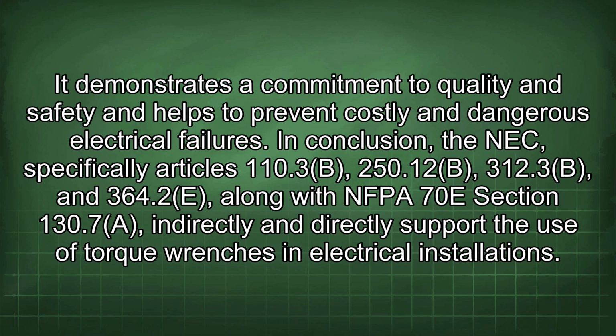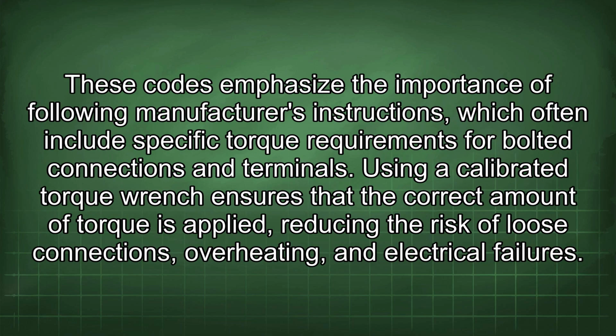In conclusion, the NEC, specifically Articles 110.3b, 250.12b, 312.3b, and 364.2e, along with NFPA 70E Section 130.7a, indirectly and directly support the use of torque wrenches in electrical installations. These codes emphasize the importance of following manufacturer's instructions, which often include specific torque requirements for bolted connections and terminals.